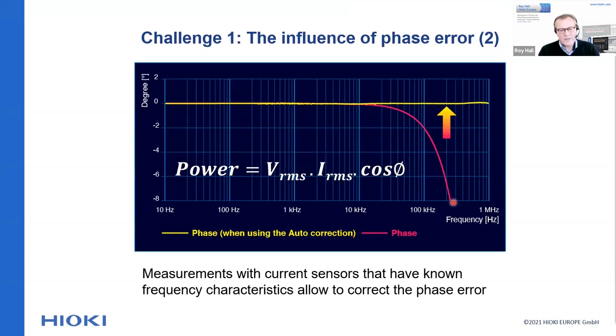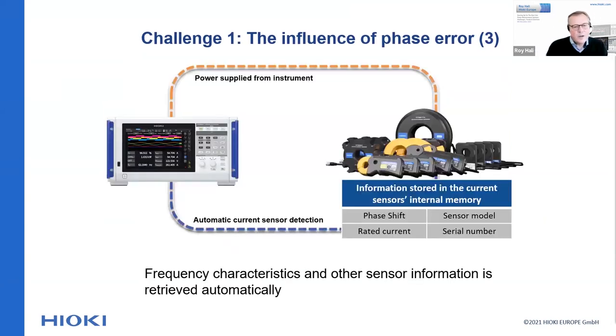The design of the Hioki current sensors guarantees a constant frequency characteristic. In other words, all the current sensors that have the same model code will have identical frequency characteristics. With this in mind, we can work out a method to eliminate the phase error. All new current sensors that are suited for power measurement have an internal memory in which the model code, the current range, the phase error information, and the serial number are stored. When the current sensor is connected to the new PW8001 power analyzer, it will be recognized automatically. And all the relevant information, like the phase error, model number, serial number, and rated current, will be registered in the PW8001.